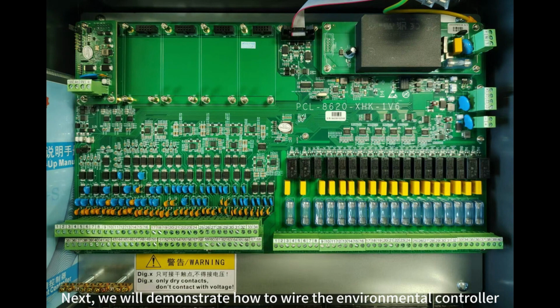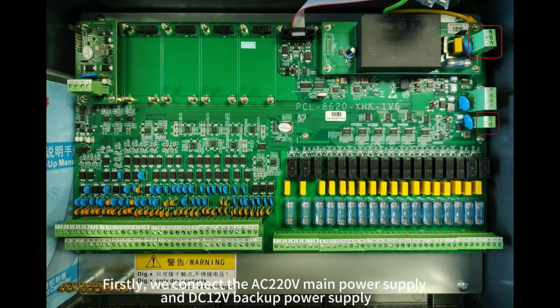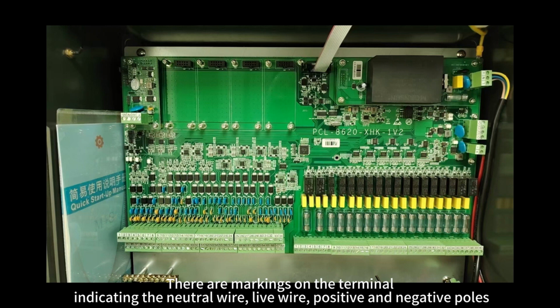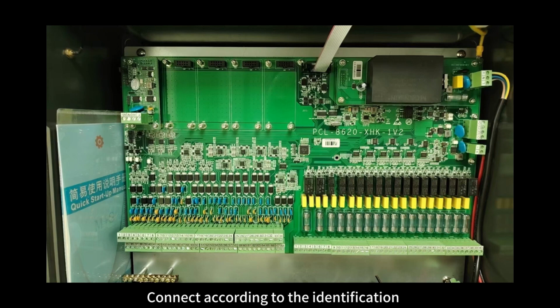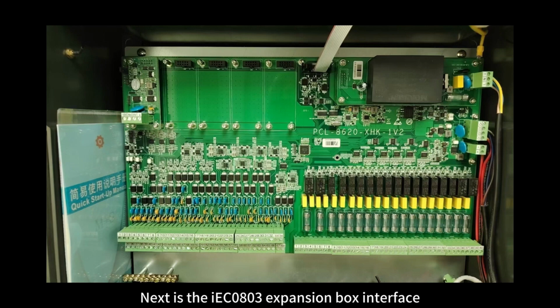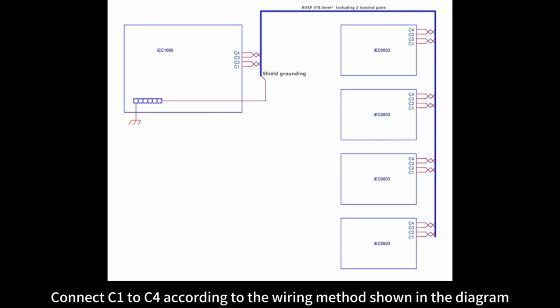Next, we will demonstrate how to wire the environmental controller. Firstly, we connect the AC 220V main power supply and DC 12V backup power supply. There are markings on the terminal indicating the neutral wire, live wire, positive and negative poles. Connect according to the identification. Next is the IEC 0803 expansion box interface. Connect C1 to C4 according to the wiring method shown in the diagram.